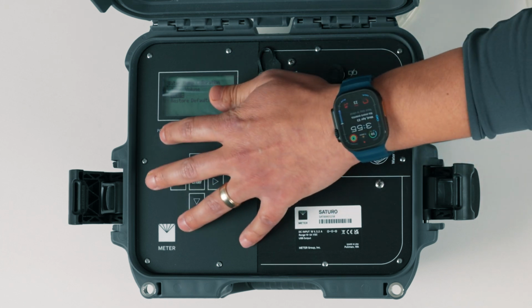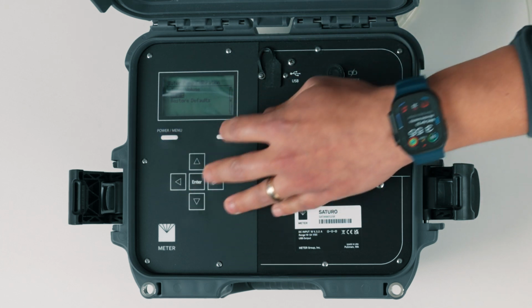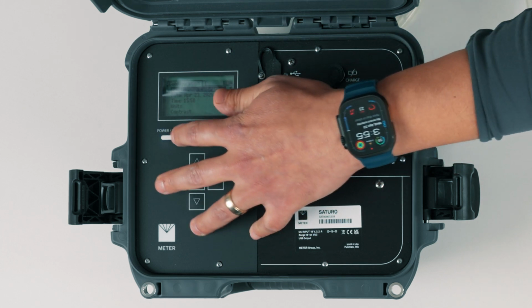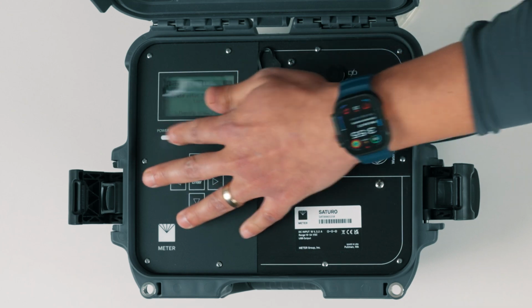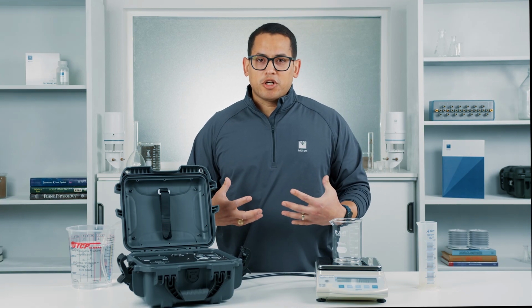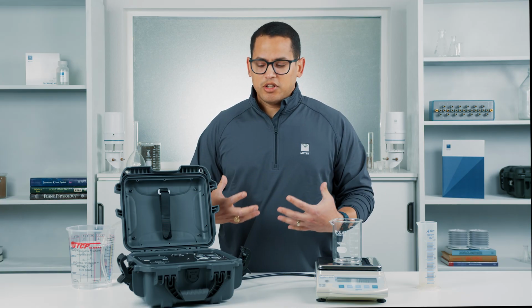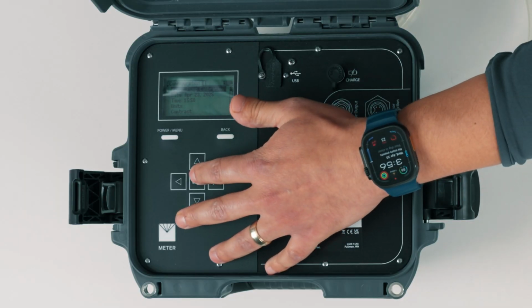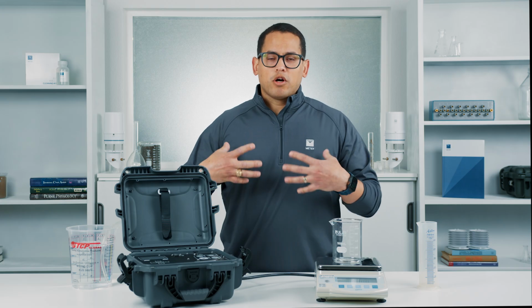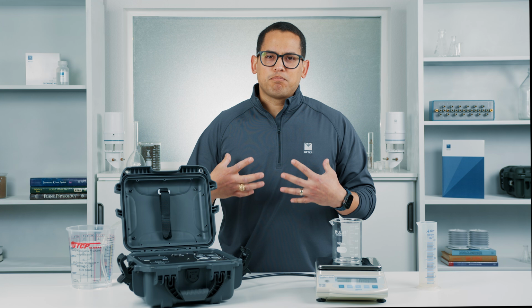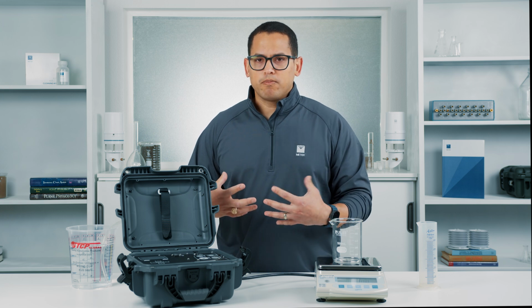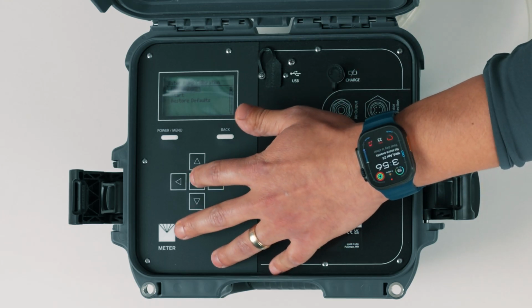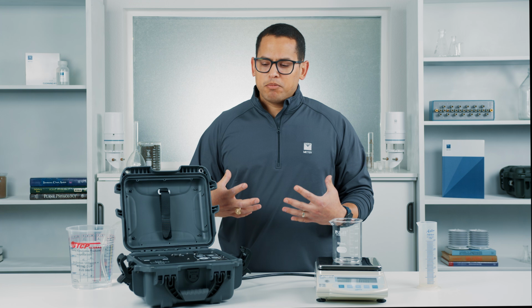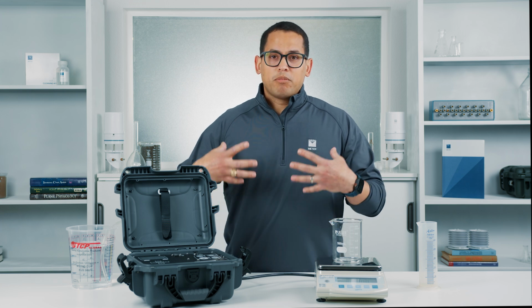In order to do this, we can navigate to this screen by pressing the menu button over to the configuration tab. On the configuration tab, we're going to use the water pump calibration process again. And this time, for our type of calibration, we're going to select a mass calibration instead of the volume. Now that we have that set up, we can go to the Start button.